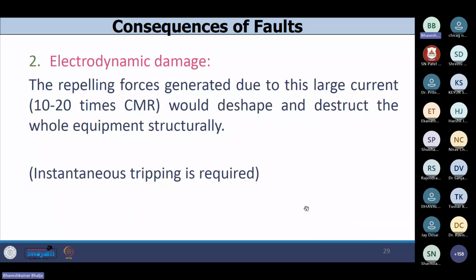And the second damage is electrodynamic damage. Because of the very high magnitude of current, very high forces are generated, and that is going to destroy the whole equipment structurally, which means your equipment may get damaged. So these two things happen whenever a fault occurs. Our task as an engineer or utility person is to detect the fault and isolate the system before thermal or electrodynamic damage occurs in the system.